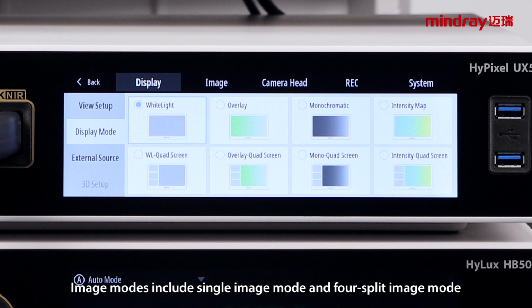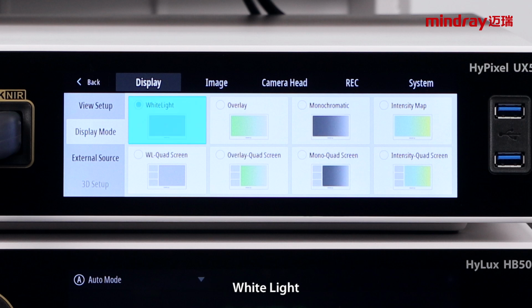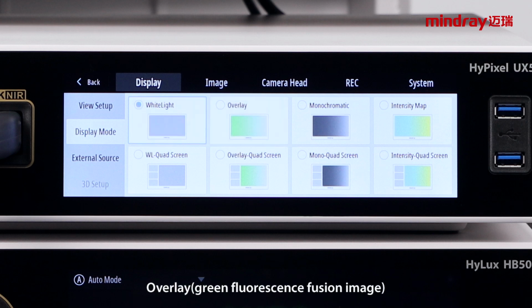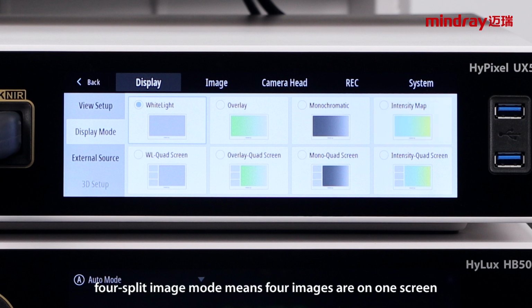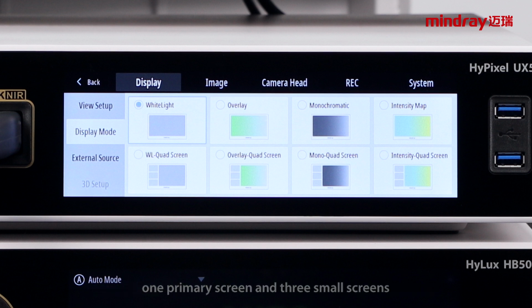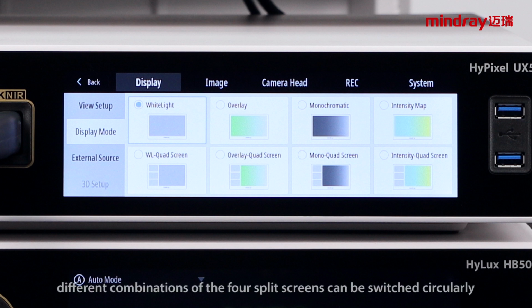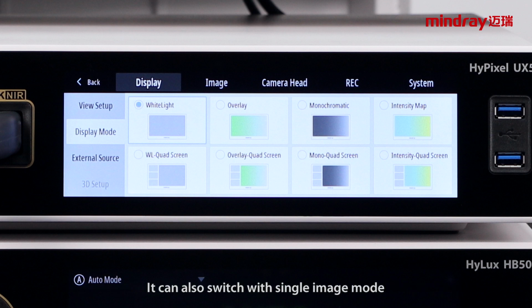Image modes include single image mode and 4-split image mode. Single image mode includes white light, overlay, green fluorescence fusion image, monochromatic, black and white fluorescence image, intensity map, and color fluorescence image. 4-split image mode means 4 images are on one screen, 1 primary screen and 3 small screens. For easy comparison, different combinations of the 4 split screens can be switched circularly. It can also switch to the single image mode. Note: to perform fluorescence surgery, Mindray G-series telescope and ICG are required.